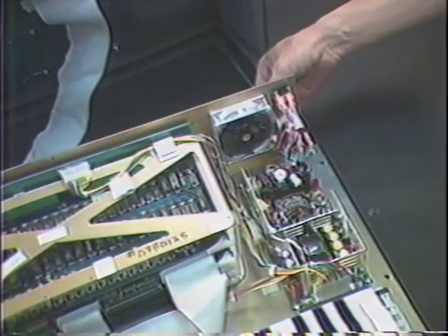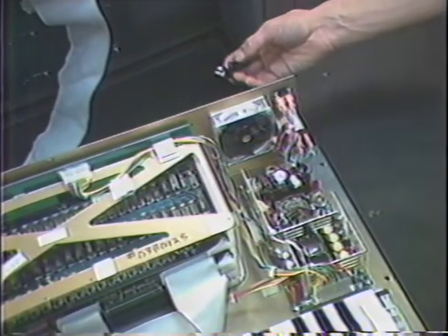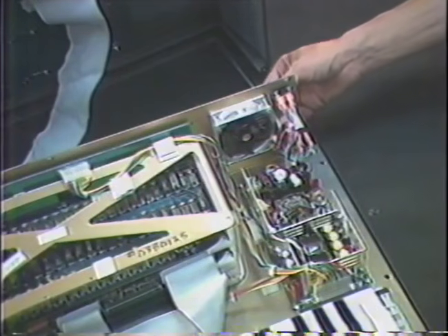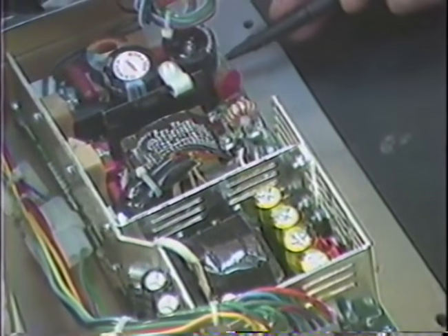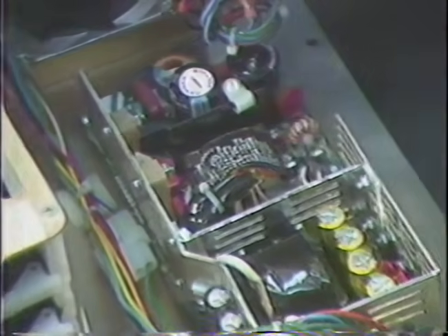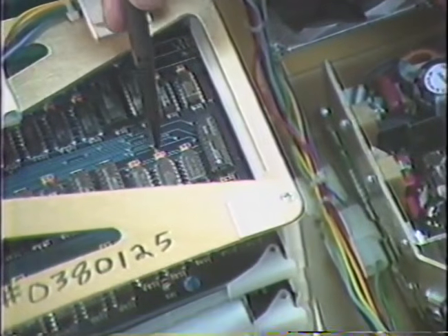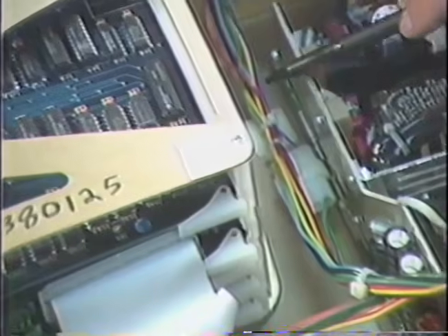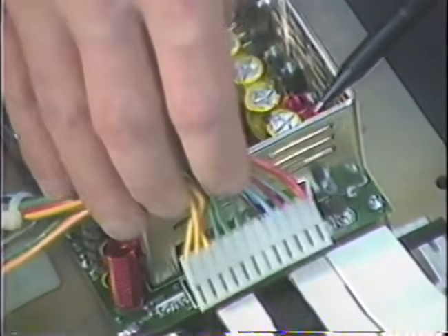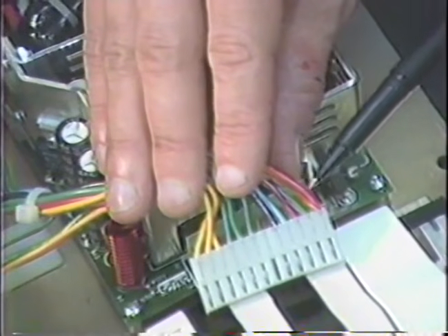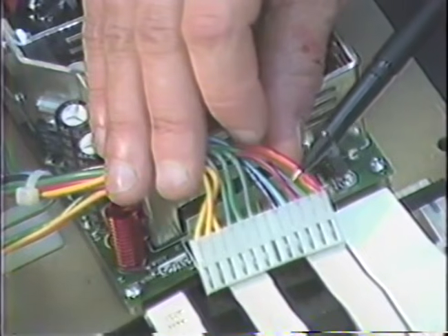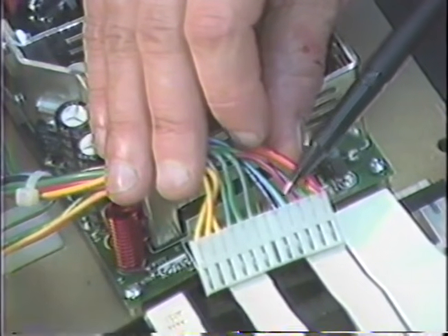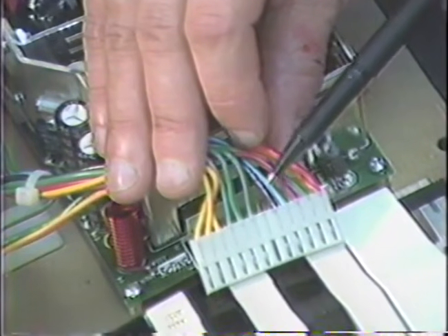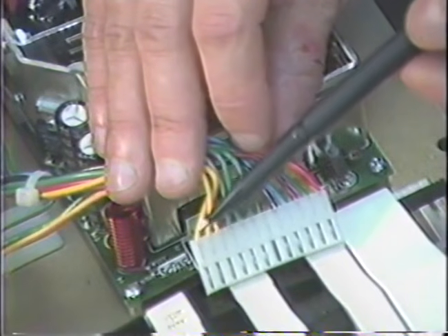No power. Check the AC fuses located to the rear of the E3. If they are blown, there is a reason, so before you install new ones, check the following. The power supply varistor located at VR1. The power supply fuse. Blown decoupling capacitors on PCBs. A bad DC wire harness. When the supply is working, you should be able to read plus 12 volts on the orange wire, digital ground on the green wire, plus 15 on the red wire, analog ground on the blue wire, minus 15 on the black wire, and plus 5 on the yellow wires.